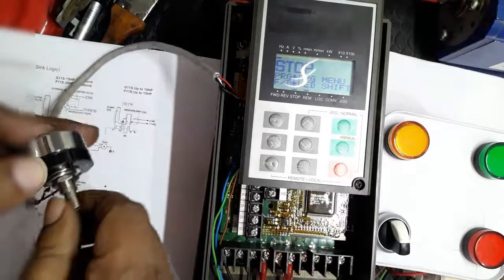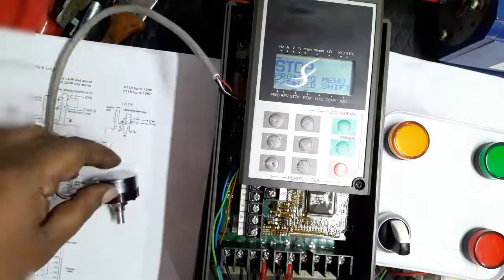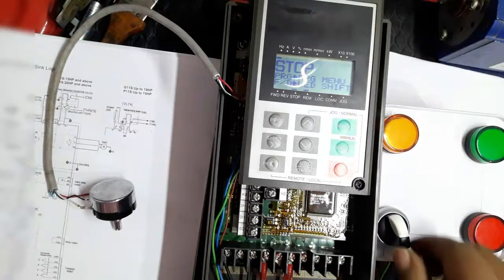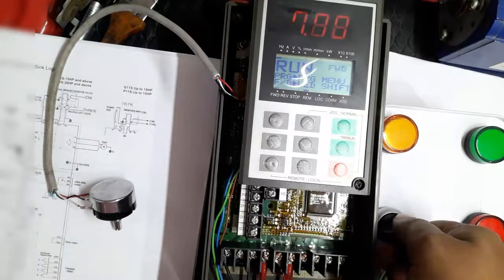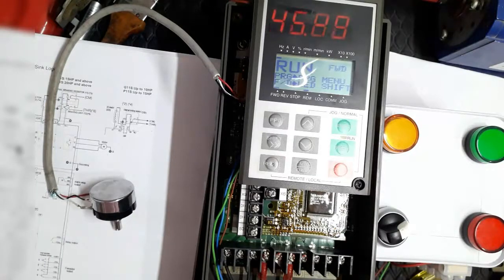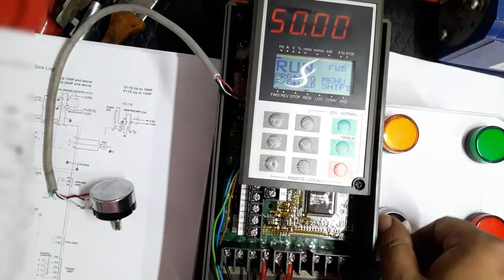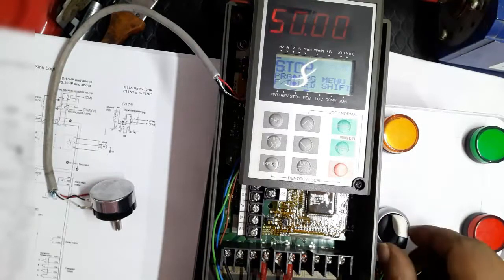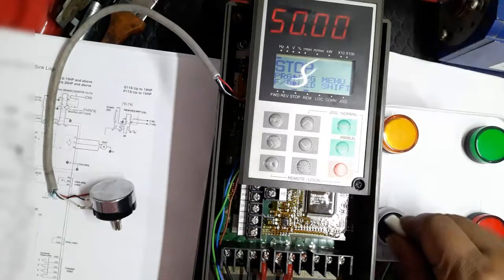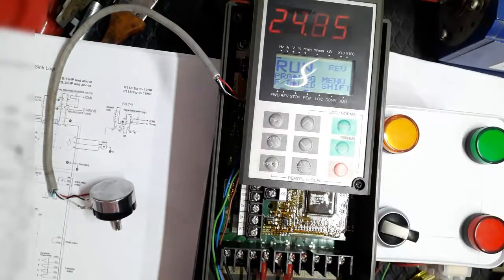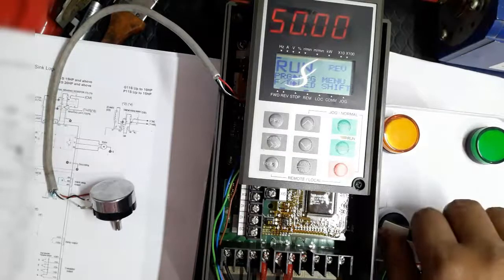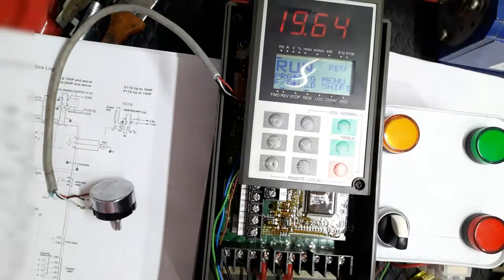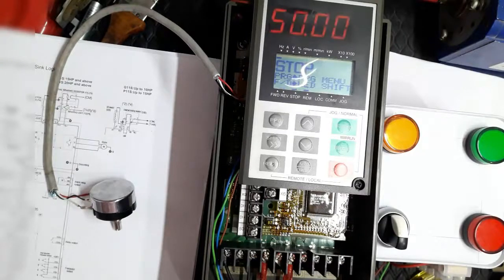So in this way, we can externally operate the Fuji G11 inverter by potentiometer and selector switch. The selector switch is used for forward and reverse operation, and the potentiometer for increasing and decreasing frequency and controlling motor speed. Thank you for watching. Don't forget to like and share the video. Please subscribe to the channel.